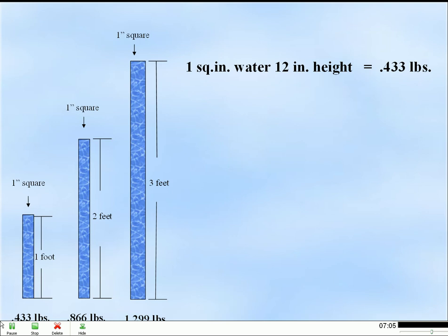Many times a plumbing inspector requires the soil system to be tested by having all openings tightly closed and a 10-foot vertical pipe filled with water for a minimum of 15 minutes. This subjects the system to a 4 to 5 psi pressure throughout to verify a leak-proof system.